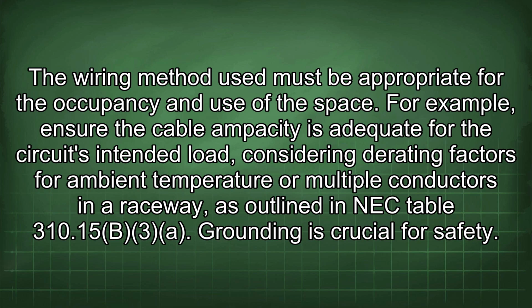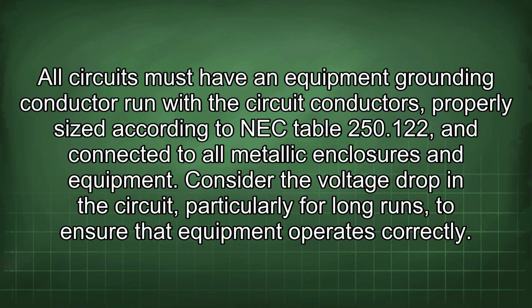For example, ensure the cable ampacity is adequate for the circuit's intended load, considering derating factors for ambient temperature or multiple conductors in a raceway, as outlined in NEC Table 310.15(B)(3)(a). Grounding is crucial for safety. All circuits must have an equipment grounding conductor run with the circuit conductors, properly sized according to NEC Table 250.122 and connected to all metallic enclosures and equipment.